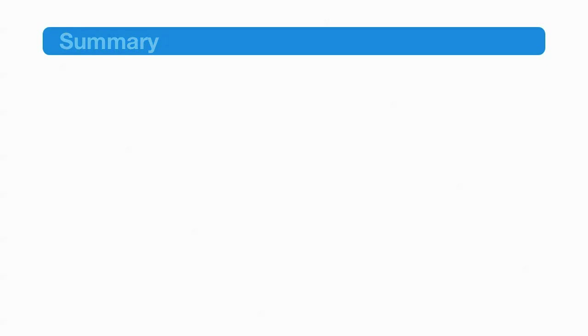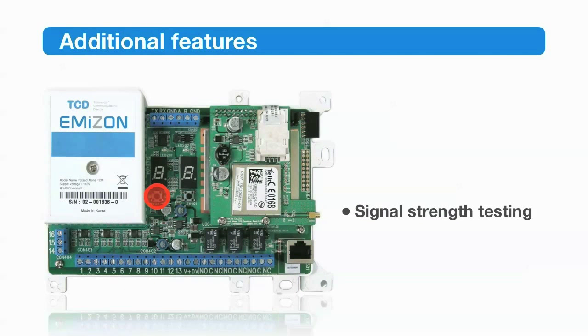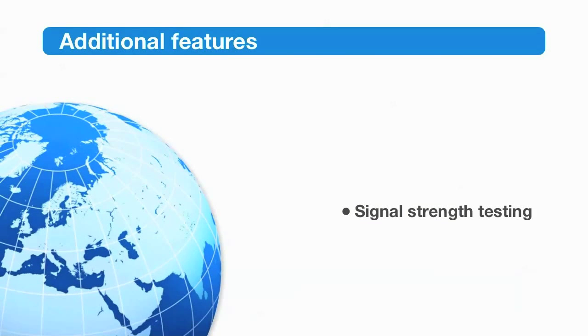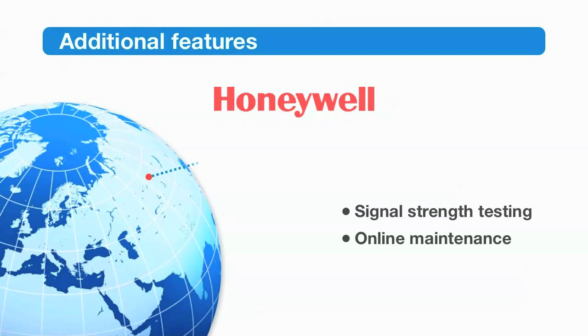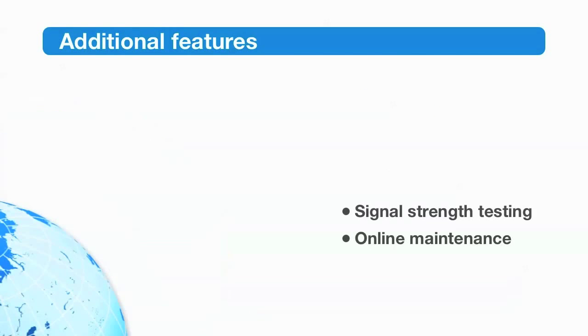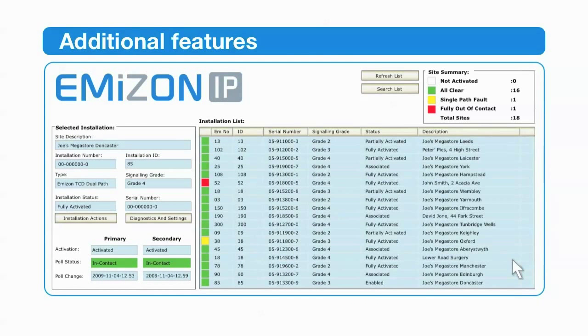The TCD is more than a dual-path signalling device. Additional features include signal strength testing — by simply pressing lightly on the mode button, GS followed by a number between 1 and 31 will appear on the display; a reading of 12 or more is acceptable. You can also use the TCD for upload/download from your alarm panel over broadband. Our traffic light service shows you the status of your alarms right across your sites, helping you diagnose and solve problems in seconds.